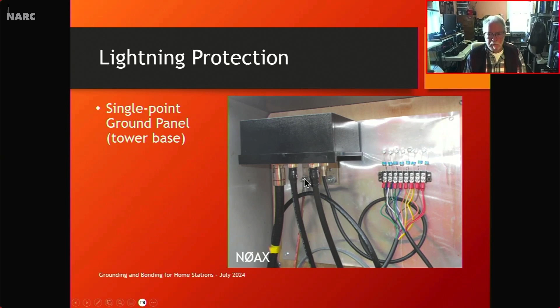You need to bond all of the earth connections outside your residence together. That's required by law in the United States, and you can see our ground rods here. I might have one for my electrical panel, one for my telephone service, one for cable television. If I mount an antenna on my house, I'm supposed to run a heavy wire down to an earth electrode of some sort. So if these aren't connected together with wire, what are they connected with?